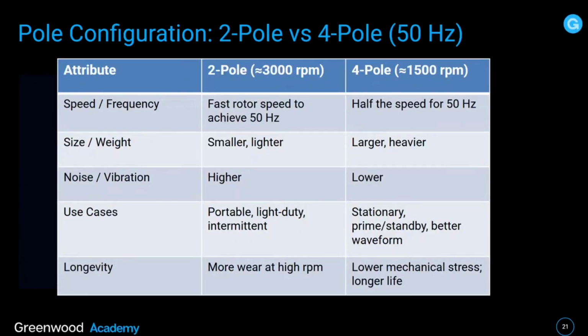Pole configuration, 2-pole versus 4-pole. Now you can see in this little table, we've got the attribute, 2 poles versus 4 poles, and the differences. For example, when it comes to longevity, the 4-pole is going to last longer because there's a lower mechanical stress, which leads to a longer life. The rotor speed, if you're looking at frequency, is much faster in a 2-pole compared to, say, a 4-pole. So the general rule of thumb is a 4-pole GENSET is going to last longer than a 2-pole.